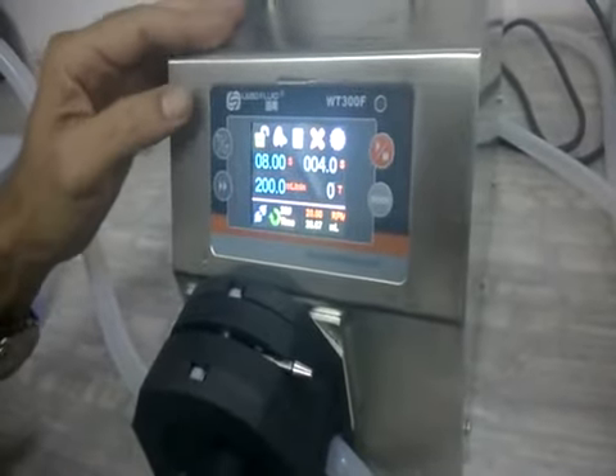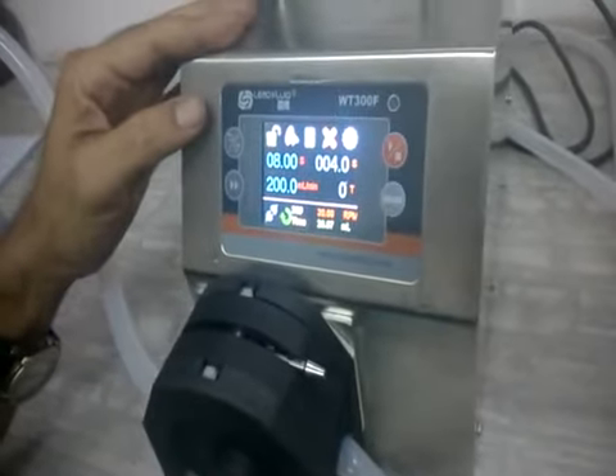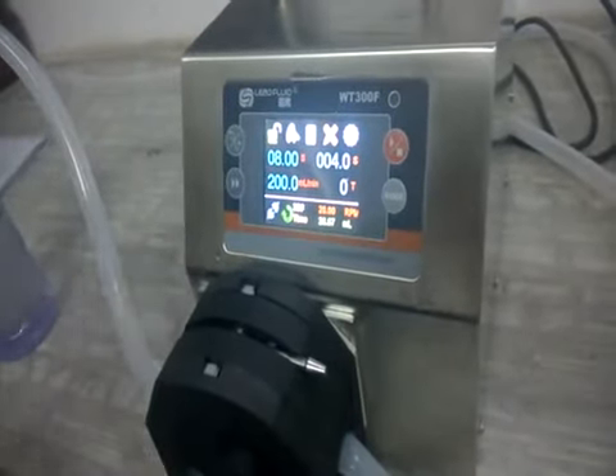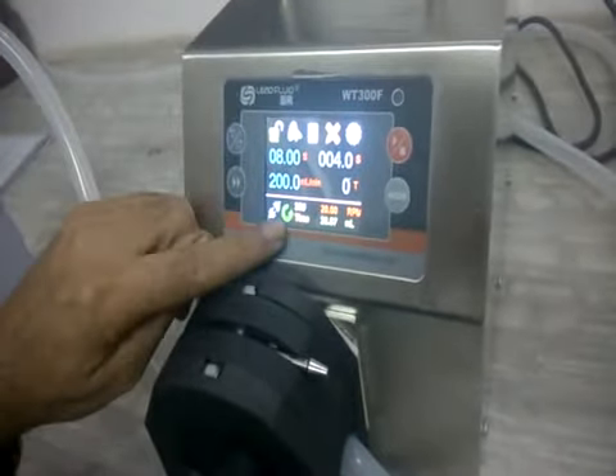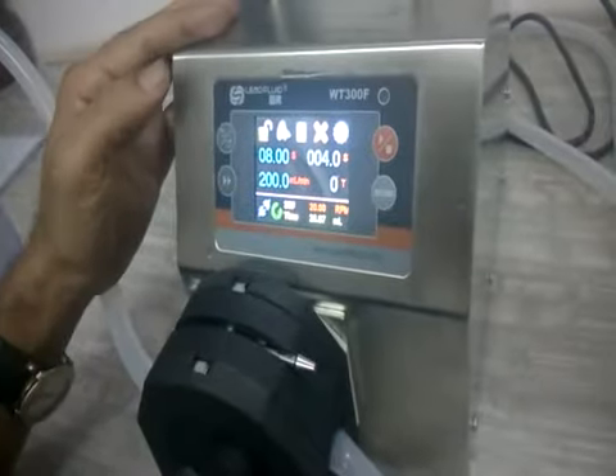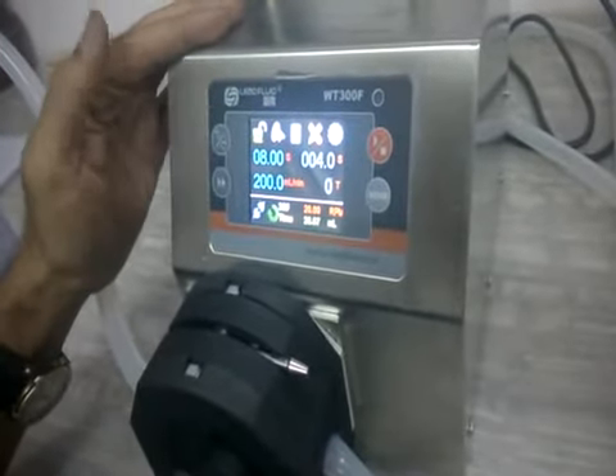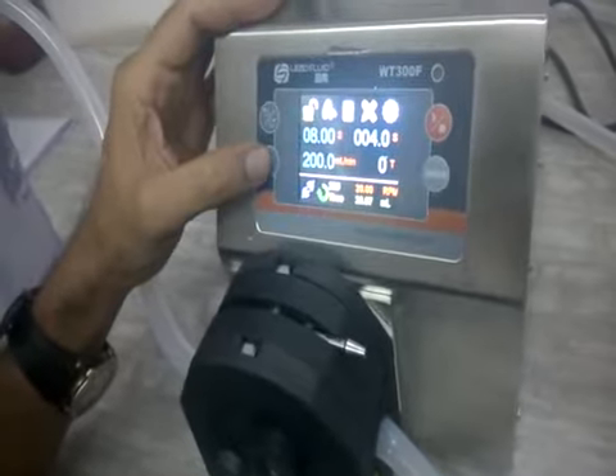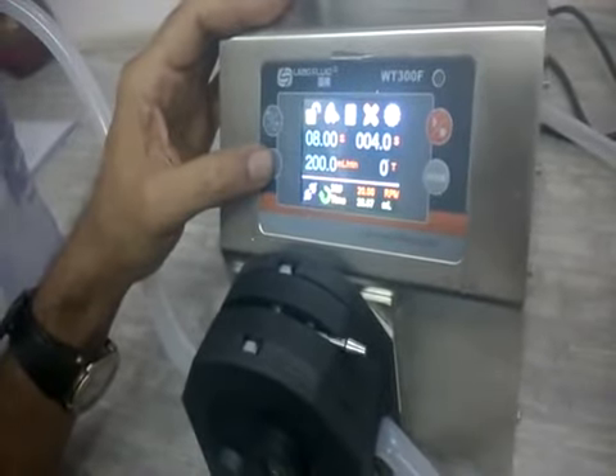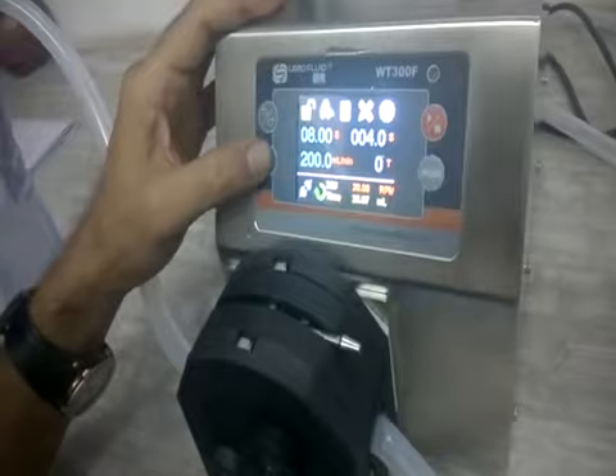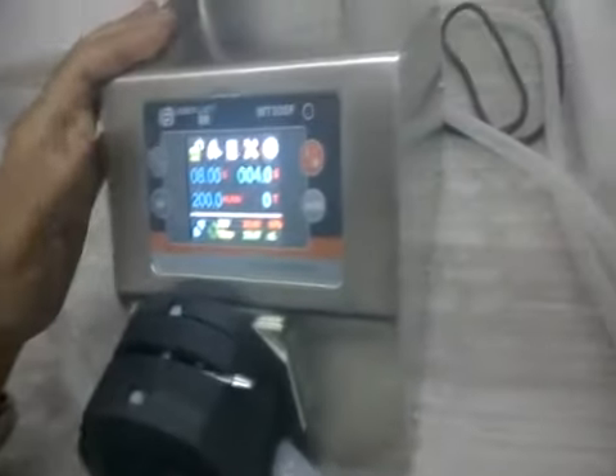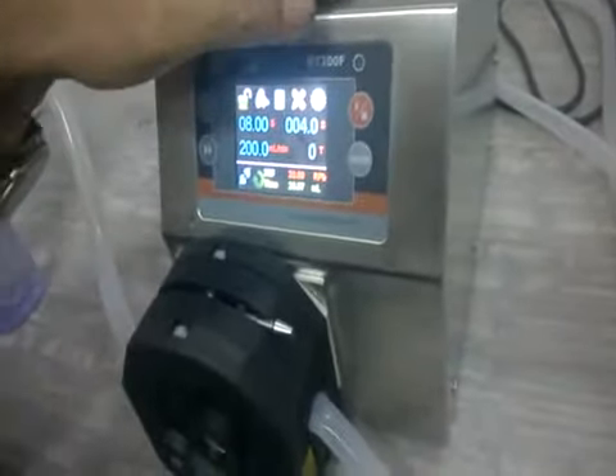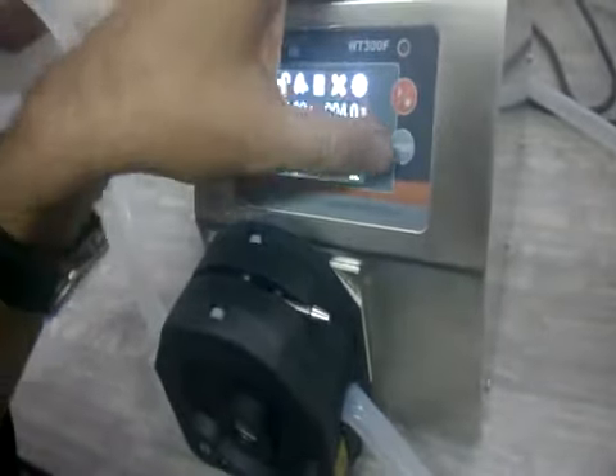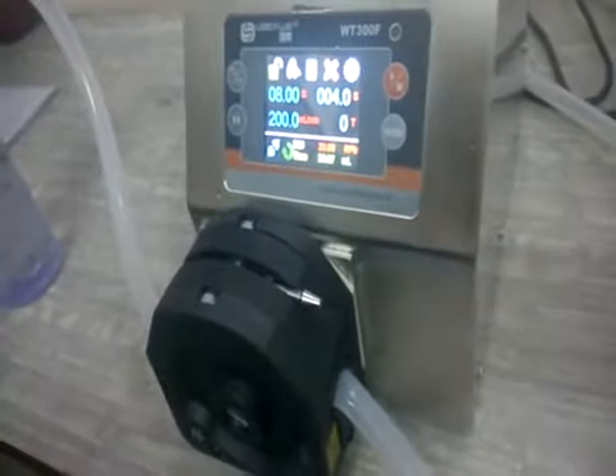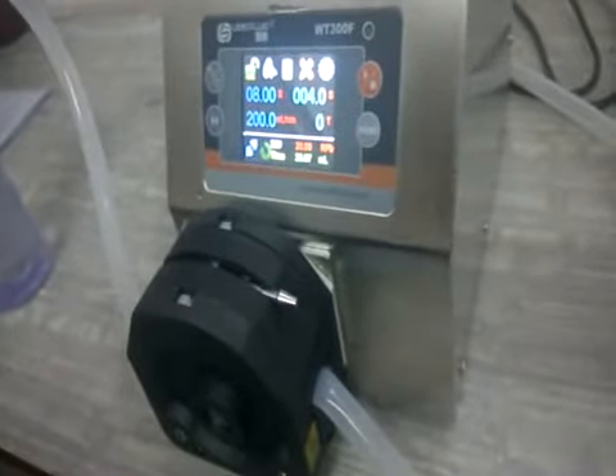If you want to rotate anti-clockwise, from this side it will suck and this side it will dispense. You press it and you can see that the direction is anti-clockwise. Again I am making it clockwise. This is a flushing function. If you want to flush the tubing very fast with your solvent, you can press it and it flushes very fast. And this is start and stop. And this is your mode key, which is a very important key.